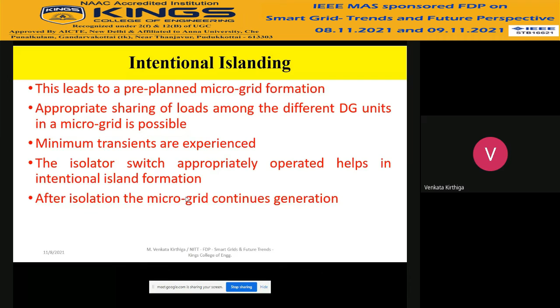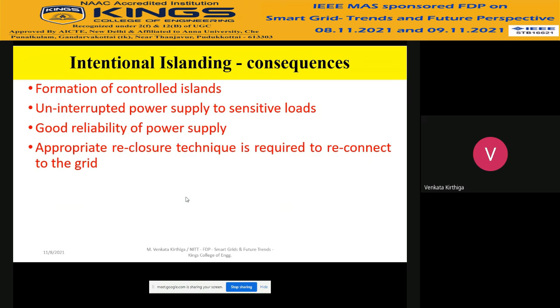After undergoing intentional islanding, you get formation of controlled islands. Now the problem is restoration. You should have a restoration mechanism in hand before attempting intentional islanding, because reclosure is not very simple. You should be ready with a mechanism to reclose at the appropriate instant, or to decide when it is not safe for the system to continue in island mode. That risk, or challenge, lies in your hands.